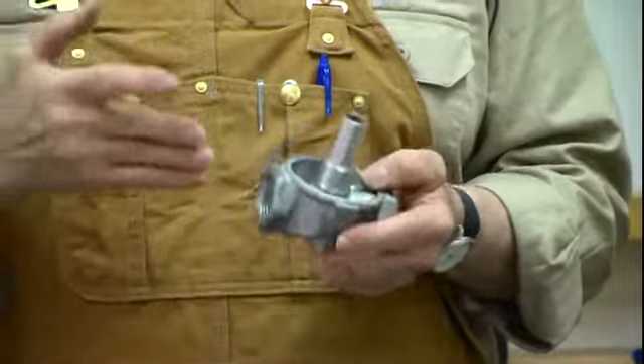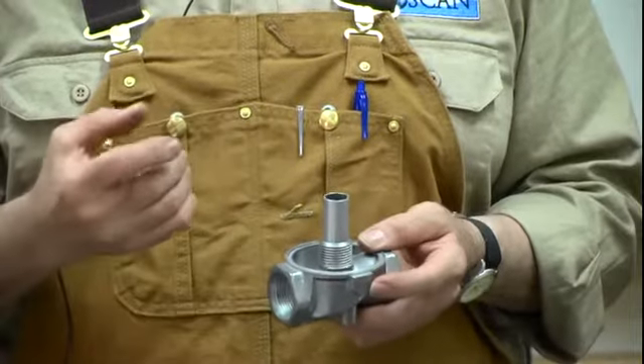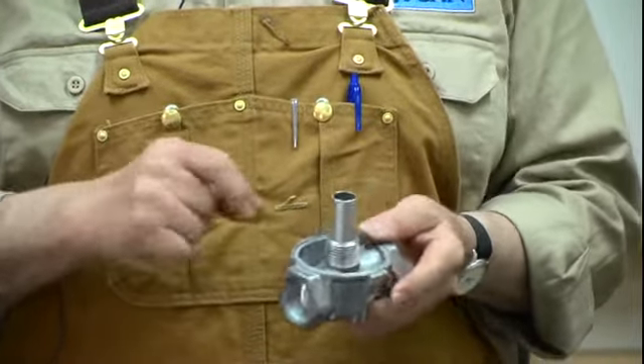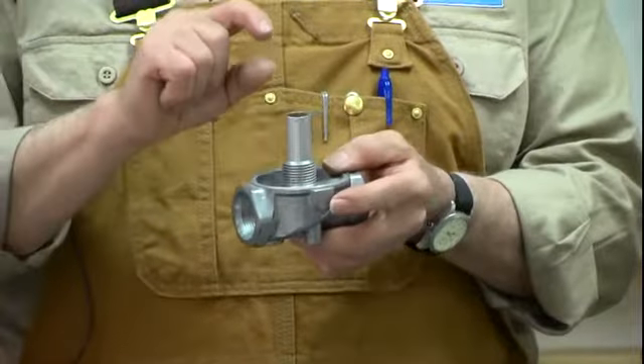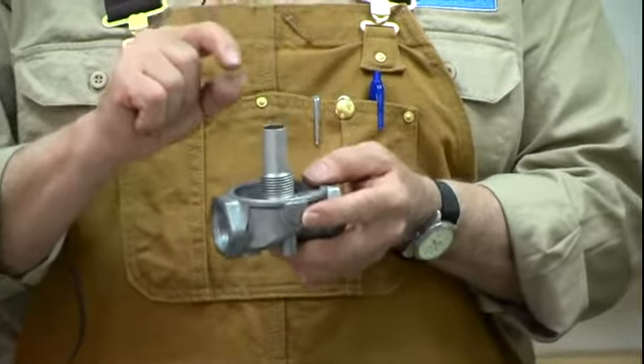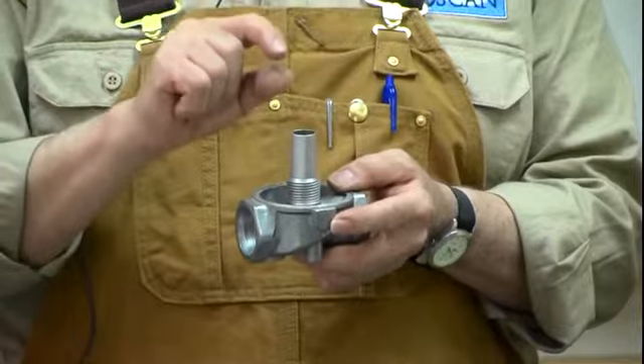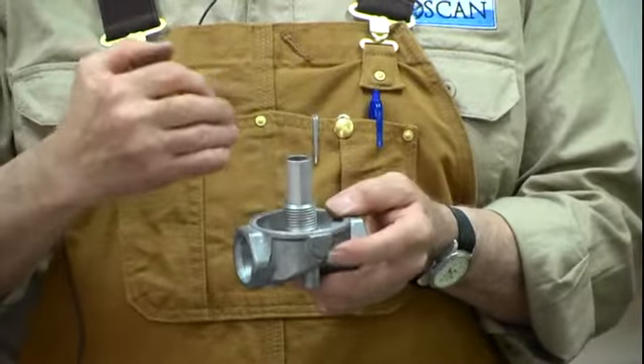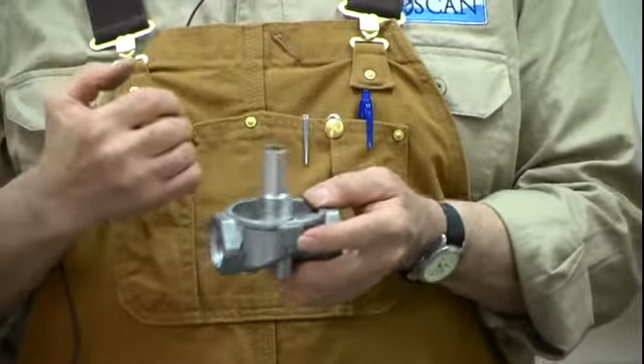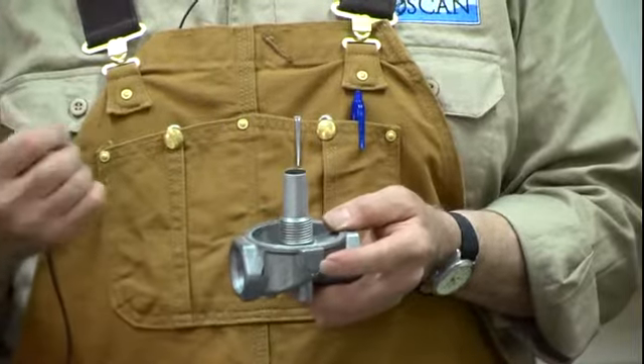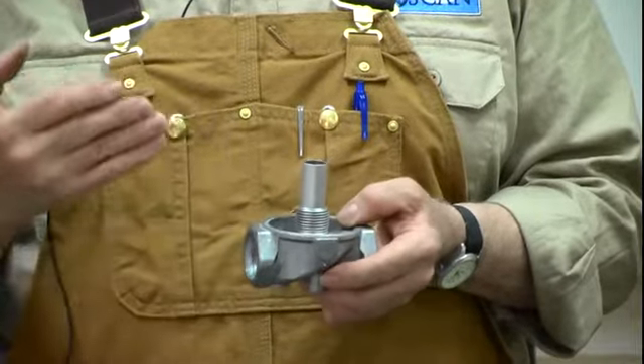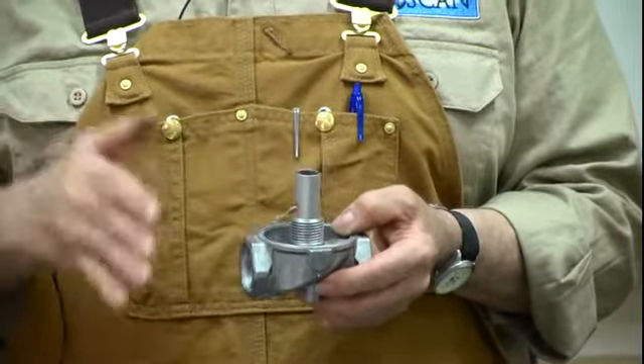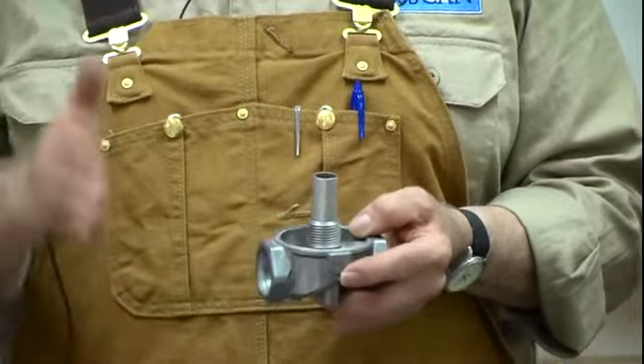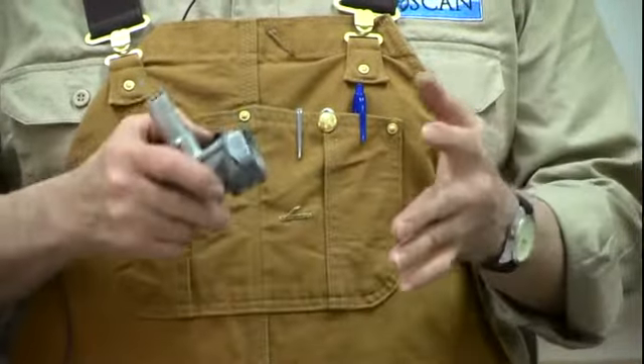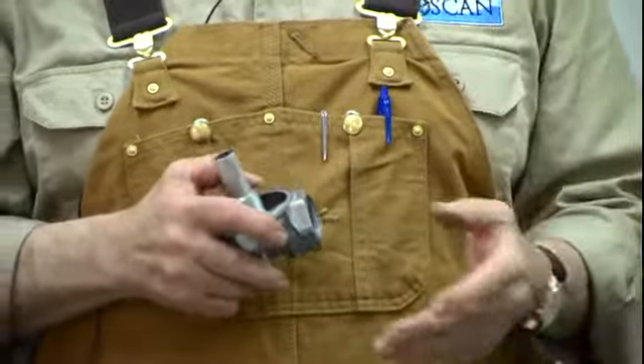Ours works 2 ways. One, there's a membrane in that canister which absorbs energy. The second, we want some vapors, some gases, either air or diesel fumes trapped at the top of the canister. That gives a place for the volumetric fluctuations to go on the fuel transfer pump. Diaphragm pumps and piston pumps go up and down. And when they go up and down, a series of check valves have to open and close.